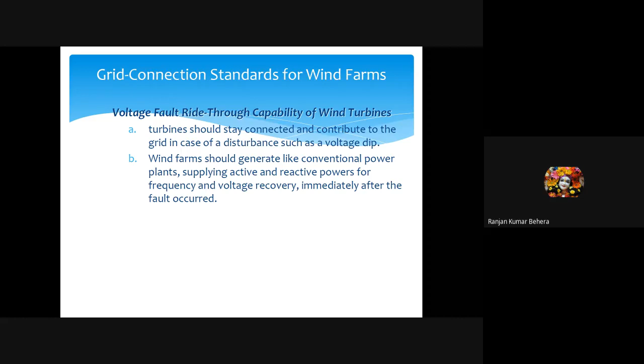So a wind farm should generate like a conventional power plant, supplying active and reactive power for frequency and voltage recovery immediately after the fault occurs. If you see the grid code, at time 0 there is a fault, and the voltage is nearly 15% of its value. At that 15% voltage level, your generator should still be connected with the grid. You can see that around 150 to 200, up to 400 milliseconds, there is this very low voltage of 15%.